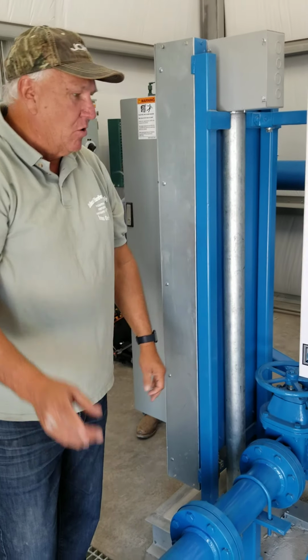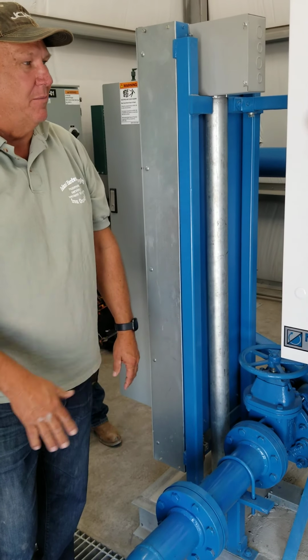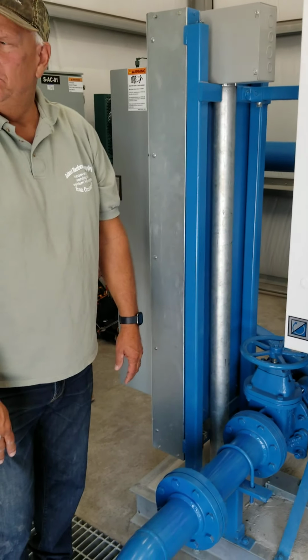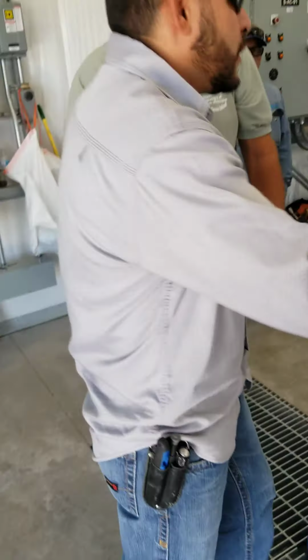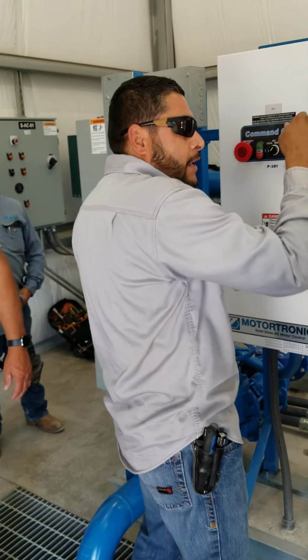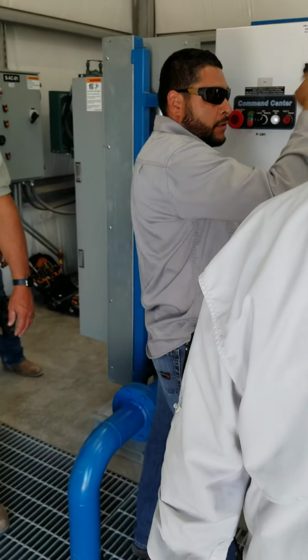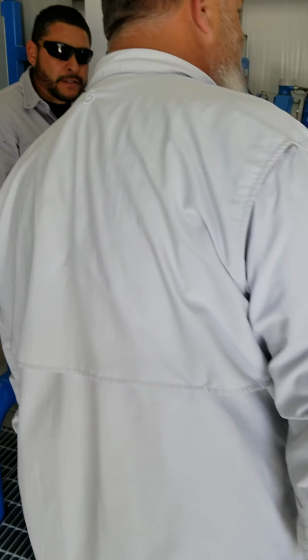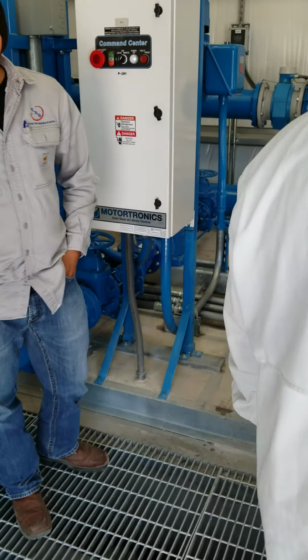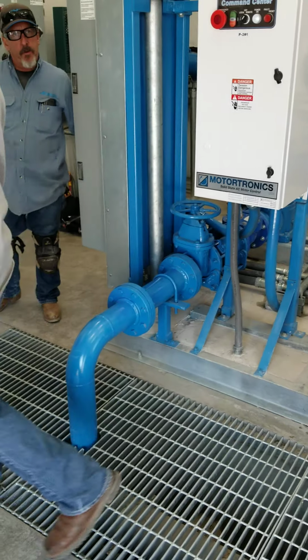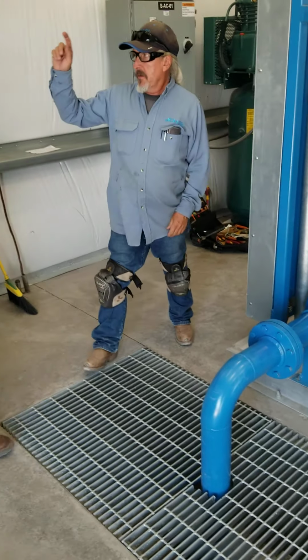But if you want, I'm going to open up a valve and you guys watch it come on. The other thing, if one pump is out of service, you leave this off, and my system will skip this one and alternate to the next one. Okay, I understand. This panel has the main breaker for each individual pump, and then the main breaker for this panel is this one.